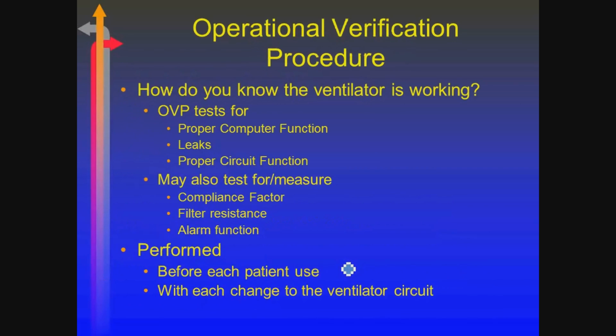Okay. Lastly, we want to talk. I think that's lastly, right? We're almost done. Something called an operational verification procedure, or what I call checking it out. Is the ventilator functional? What ends up happening in most institutions is somebody brings the ventilator back down, strips it down, cleans it, processes it, puts it back together, does a check on it, puts a little sticker or something on it, and puts a bag over it, puts it in a corner.